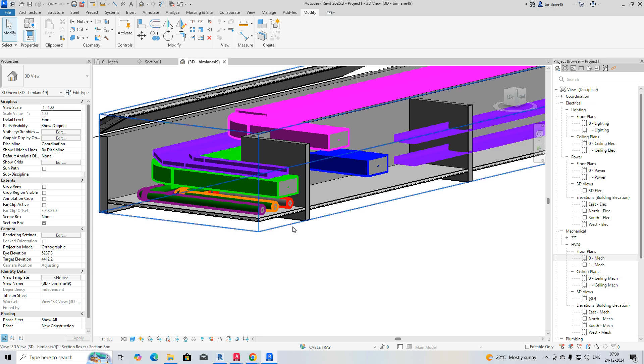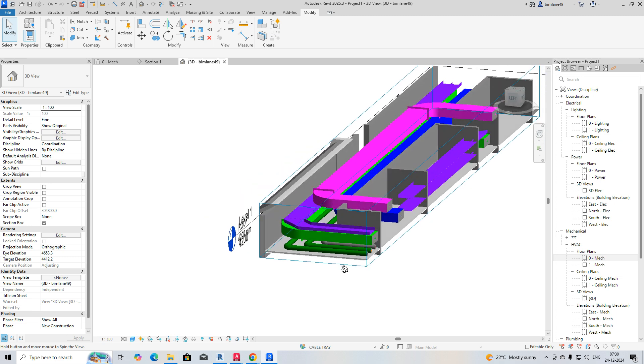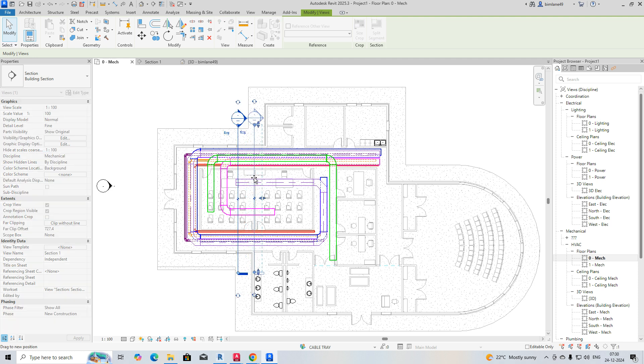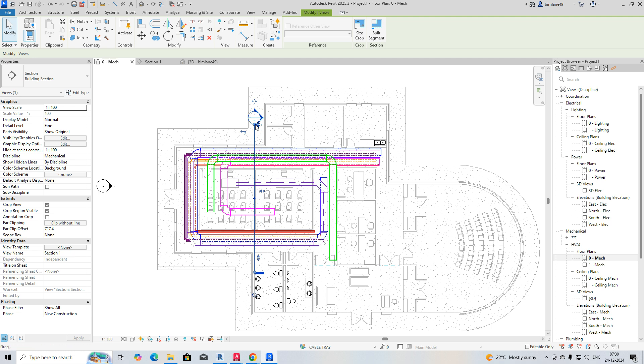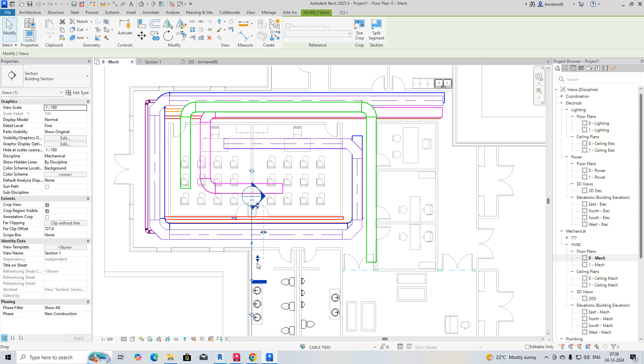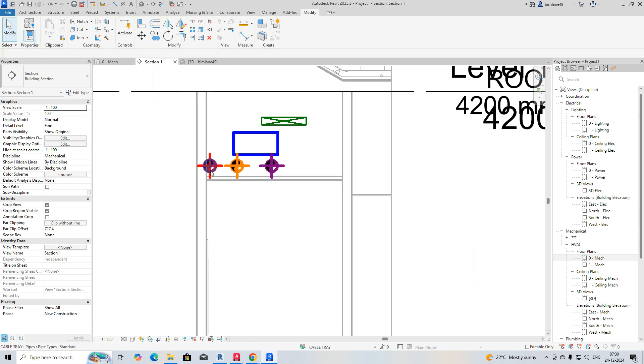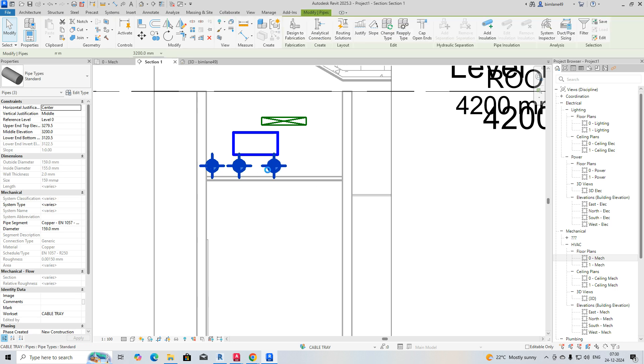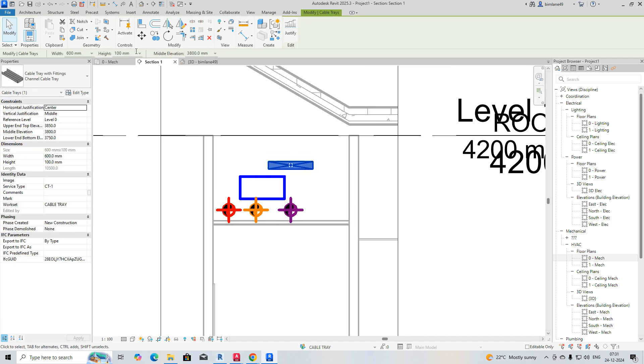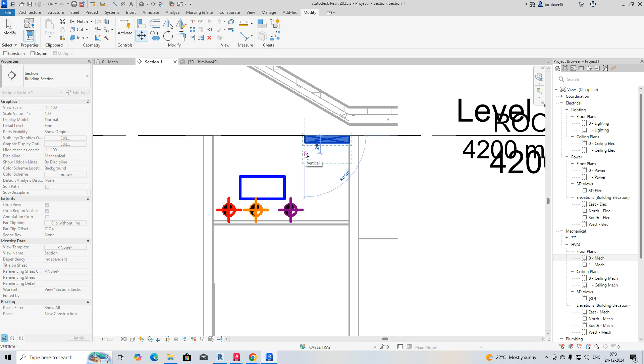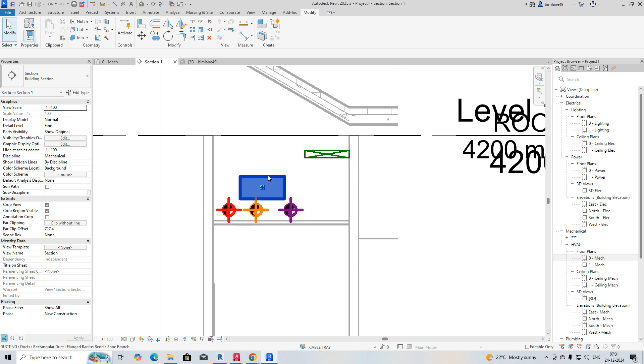Anyway, you can give whatever color you like. I have made one section — for example from here in the corridor area, we will start from this area and see how it looks. I just made one section and stretched it up. Go to view — you can see the pipes are here. First we can put the cable tray on the right side at the top, and making the distance from the top about 200mm down.